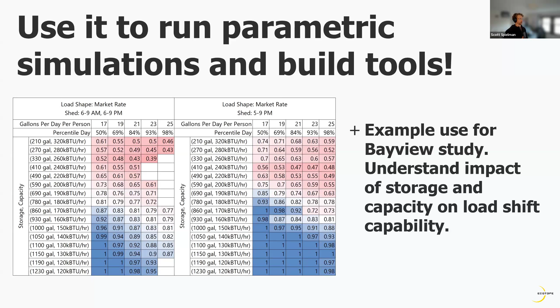Here's an example of a way that we use that backend simulator to understand the impact of storage and capacity on the load shift capability with a market rate load shape and a low income load shape. We just simulated less storage, more capacity to more storage, less capacity with the same load shift controls. And you can see as we move down there, we get a higher percentage of success rate on being able to shift load through the entire shed period.